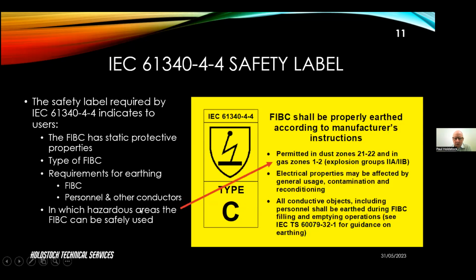And then also the important information on where the FIBC can actually be used. It's saying there that you can use that FIBC safely. It's permitted for use in dust zones 21 and 22, and also in gas zones 1 and 2 with explosion groups 2A and 2B. So it's specifying very clearly on a label where the FIBC can be used.